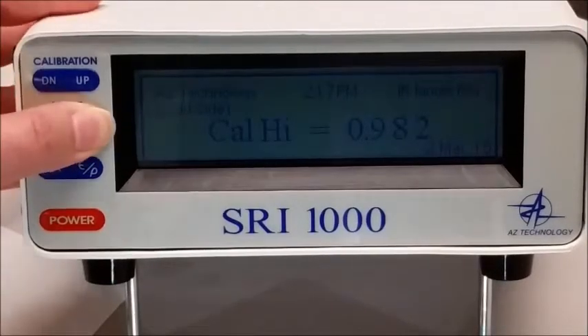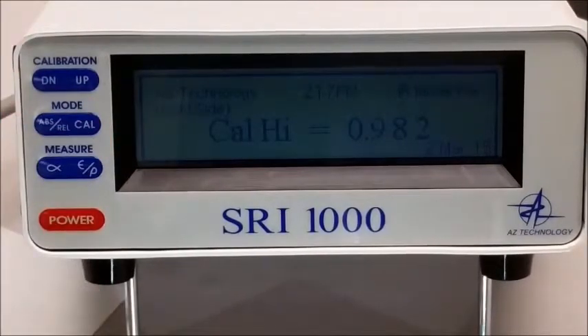By pressing the Cal button the second time, the instrument will proceed to measure the gold calibration sample. The measurement of the gold side is complete when the control display unit displays the Cal low value. Do not disturb the calibration sample until the display changes to the Cal low value. At this point, remove the gold sample and carefully place it gold side down elsewhere on the measurement head.